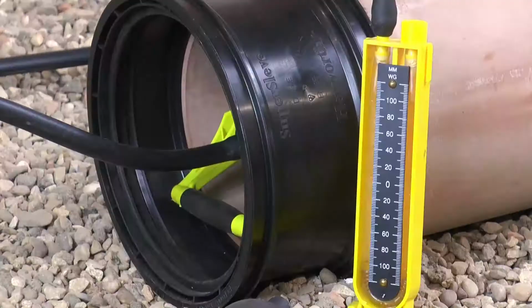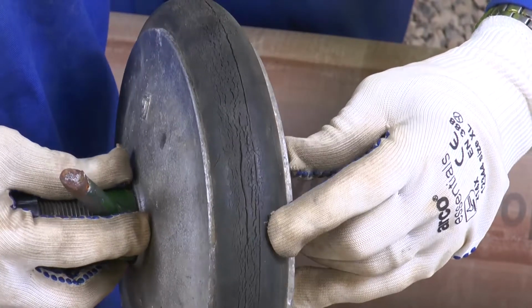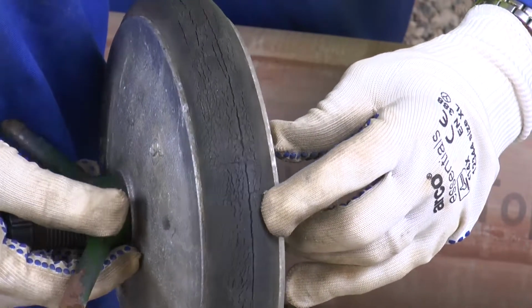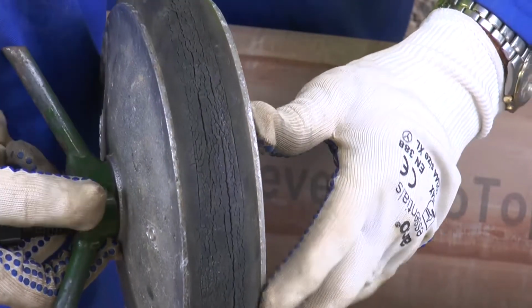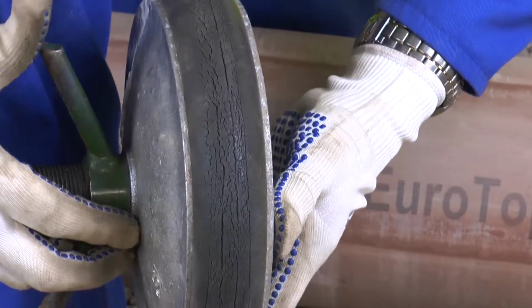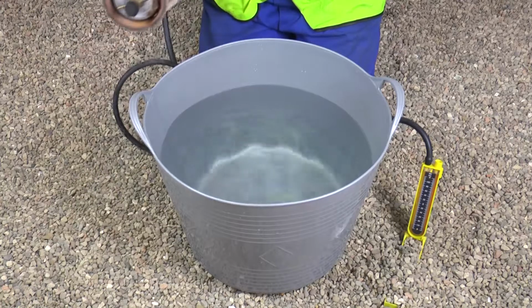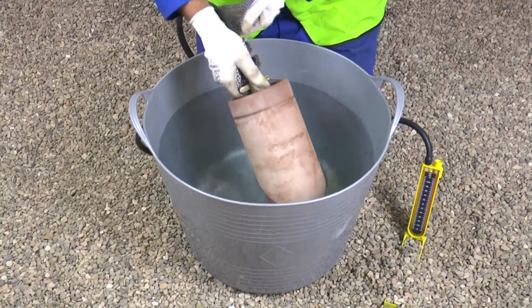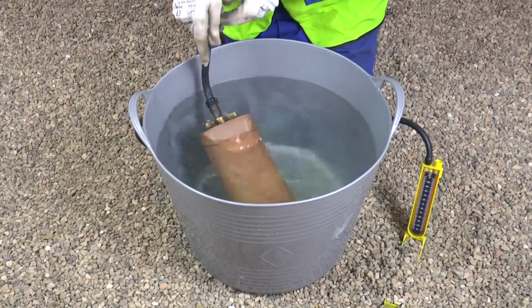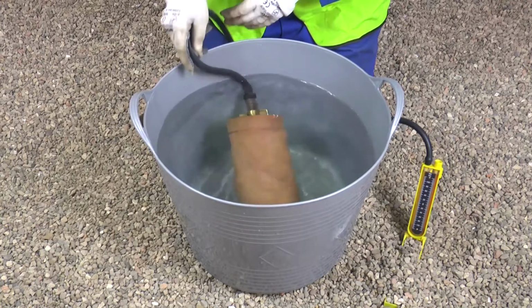The water gauge level rises, but during the test period falls below 75 mm in 7 minutes. Ensure that all the equipment is clean and in good condition. Check that the stopper rubber seals don't have any surface cracks and the end caps are tight. Connect the testing equipment to a short pipe and submerge each part underwater in turn, or completely, to identify any leaks where air bubbles escape.